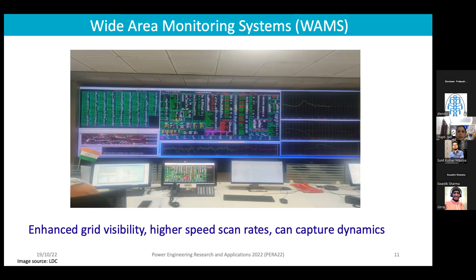This is the PMU measurement, the phasor measurement unit, which provides data at a very high sampling rate with higher speed scan rates and time-stamped measurements. This time is synchronized with GPS systems, making it more accurate. Because of the higher speed scan rates, it enhances grid visibility and can capture the dynamics of the system, making it much better compared to the conventional SCADA system.